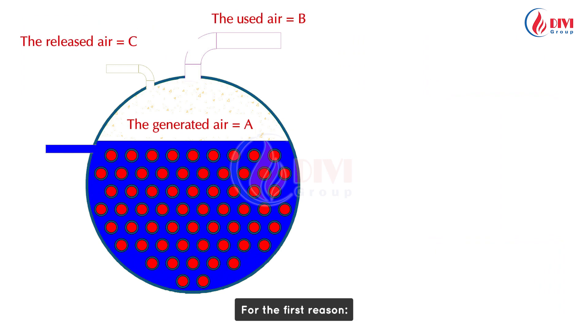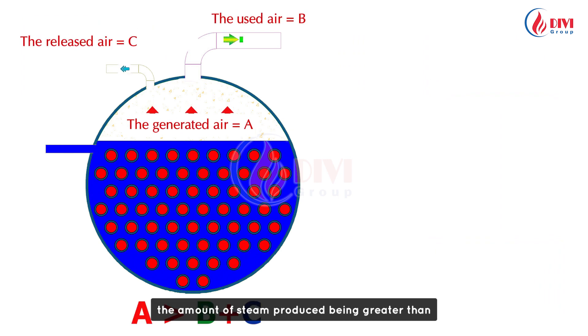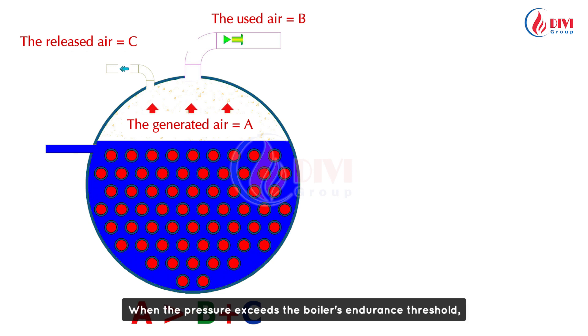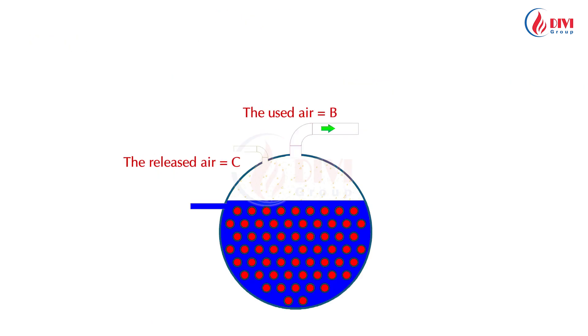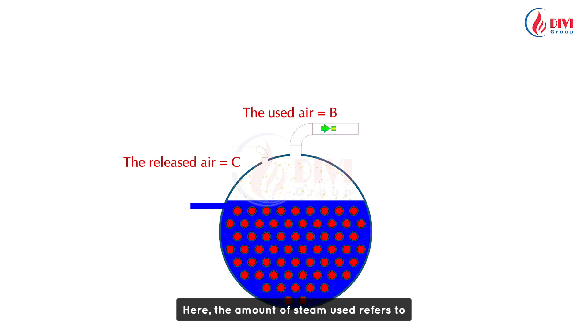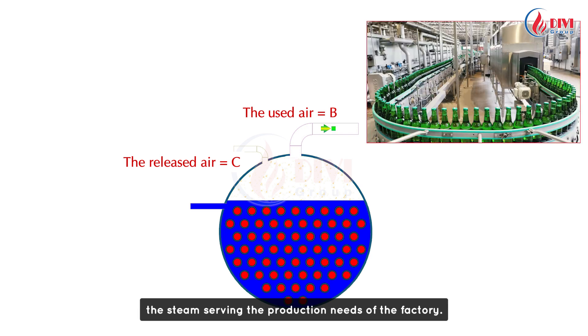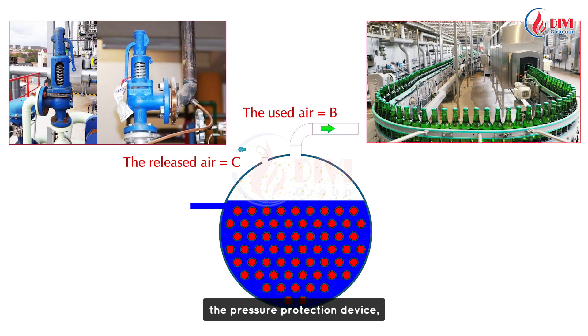For the first reason, the pressure inside the boiler increases due to the amount of steam produced being greater than the total amount of steam used and discharged. When the pressure exceeds the boiler's endurance threshold, it causes a boiler explosion. The amount of steam used refers to steam serving production needs, while the steam discharged is the amount escaping through the pressure protection device, commonly known as the safety valve.